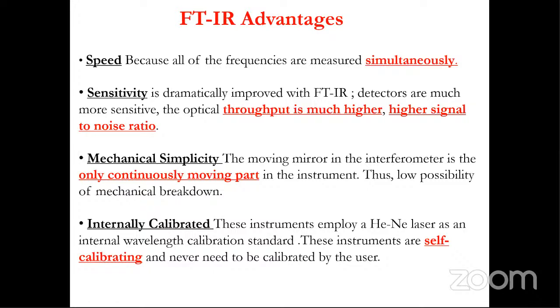The instrument has a helium neon laser as the internal wavelength calibration standard. So these instruments are self-calibrating and never need to be calibrated by the user. We can see that the calibration has already been done by the company at company level. So we need not have them calibrated by external agencies either.